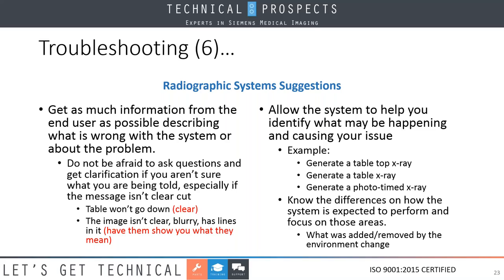However, a phototimed X-ray, now the machine's controlling the length of the X-ray. That brings in something else. It could be an ion chamber. Depending on the manufacturer, some manufacturers use calculated automatic exposures rather than an ion chamber. Again, you need to understand the difference in terms of what's happening whenever you make a change to the environment of the X-ray. This here can help you narrow down areas of problem and stuff by knowing what was added or removed from the environmental change.